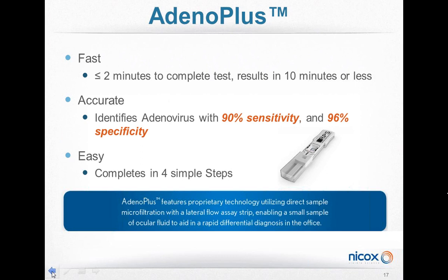The first thing you do is there's a little felt tip pad on this. You'll see it right away. Felt tip pad you put to the lower conjunctiva. Have the patient look up. You let that felt tip get completely soaked. You want enough tears in it to soak it in, even though you're pressing on the conjunctiva. Maybe 10 seconds. And after that felt pad is drenched, you then place it onto this little cartridge, and you secure it down. You'll hear it click, and you'll also feel it when it clicks in.